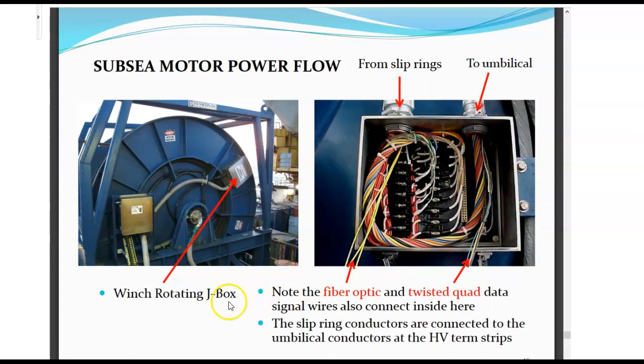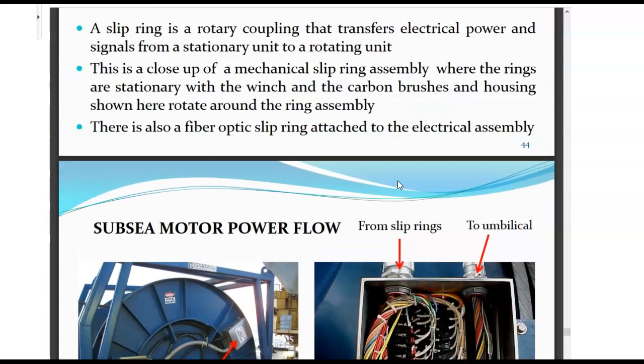Right, you want to know where to go. Alright, so this is winch rotating junction box. Okay, you should know that there's 1400 and 3000 volts here, obviously. And if there's an 8 gauge and a 10 gauge, the 8 gauge is a bigger gauge wire, that's going to be for your motors. The 10 gauge, next one down, is going to be for your single phase. Just little things like that to know in life.